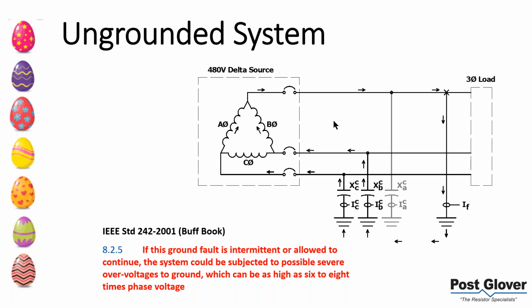The reason why I bring this up is because this is the situation where the overvoltages are the worst. You have up to 8 times your rated voltage due to potential intermittent faults, especially in regards to renewables, especially when you have long runs on your neutrals for your sources. The longer, the more likely, I would say. I don't have any specific data on that, but it's just a known thing.